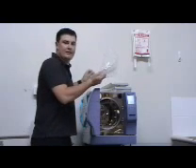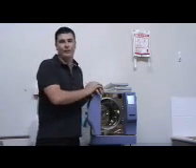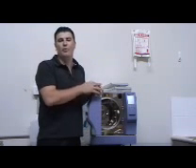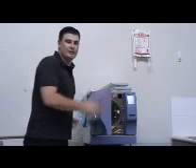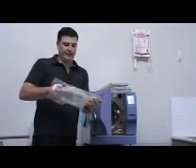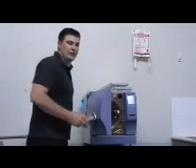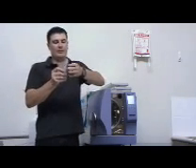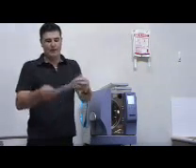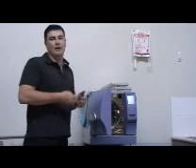There is a levelling process that has to be performed on the steriliser before starting operation of the unit. It is a fiddly process but we will walk you through it now. Once the process has been completed there will be no reason to re-level the unit unless it is moved away from its current location. To start the levelling process, remove the accessories from the bag inside the chamber of the unit. Inside your bag of accessories there should be a little bung and a little tube. These are only used during the levelling process and are not required for regular operation, but are handy to keep around in case you require the unit to be moved to another premises or into another treatment room within your practice.